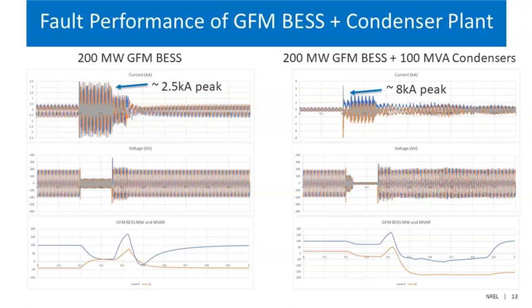But another drawback here is that in the case of synchronous condensers, there is a much higher transient in voltages during recovery, and that makes it complicated for these grid-forming battery inverters to come back to their pre-fault power level. This is why you can see on the lower graph on the right that it takes a longer time, a couple hundred, maybe 300 milliseconds or so, for the grid-forming battery source to come back online.